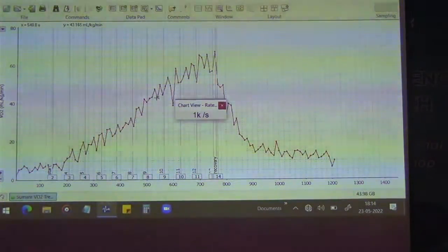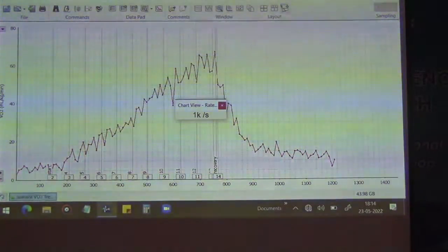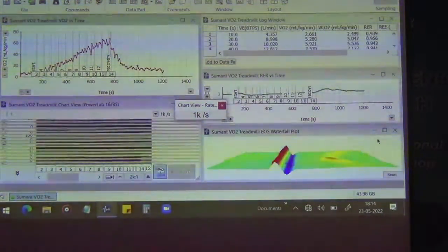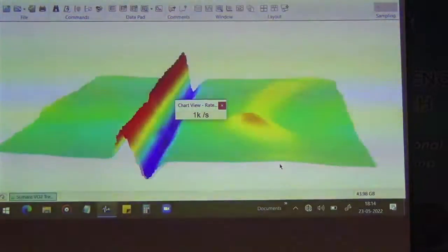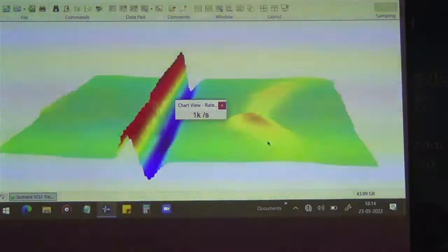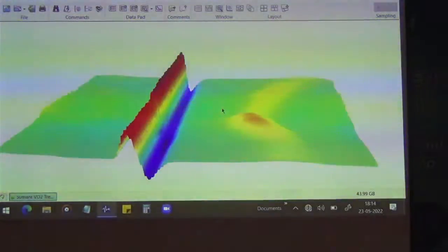You have to open the knob of the cylinder and collect the gas. The system will automatically detect. You just go for gas calibration. Then you will check the levels of CO2, VO2, all will come. If your calibration is passed, remove the gas and feed it into the gas analyzer.